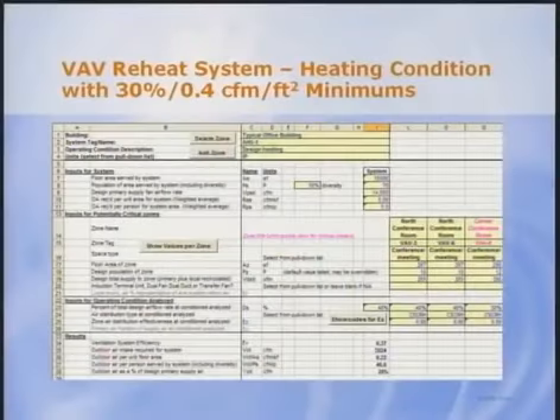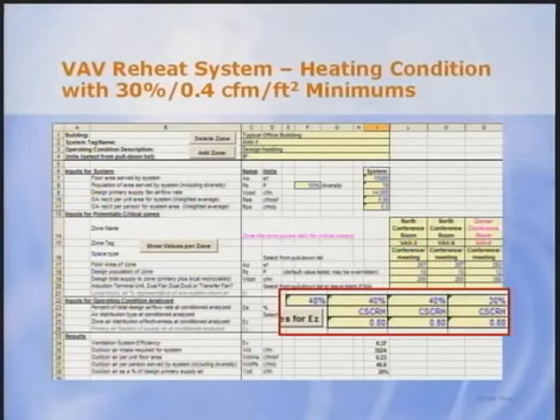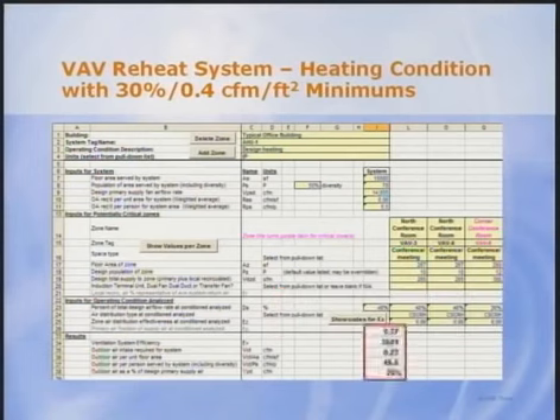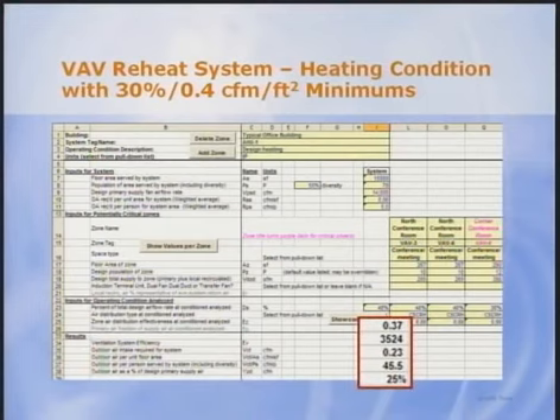In this case, we use 30% minimums, but Standard 90.1 has other exceptions that allow higher minimums in some cases. For instance, Standard 90.1 also allows minimum set points to be equal to 0.4 CFM per square foot. In this analysis, the minimums were set to the larger of 30% and 0.4 CFM per square foot. This is easily done with a formula in the spreadsheet. The minimums to the north conference room increase to about 40%, and the critical zone switches to a corner conference room. The results section shows that this scenario is possible, but only if the system outdoor air rate increased to 3524 CFM, more than double the 1565 CFM required for the cooling scenario.